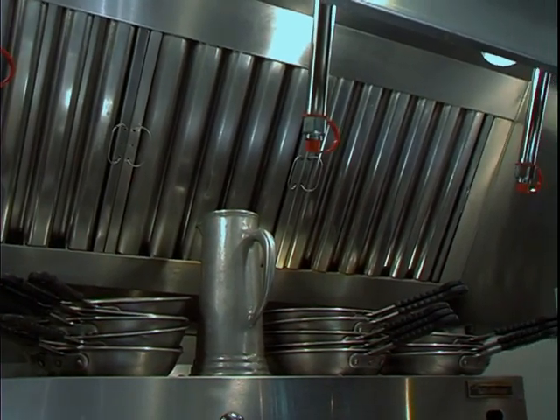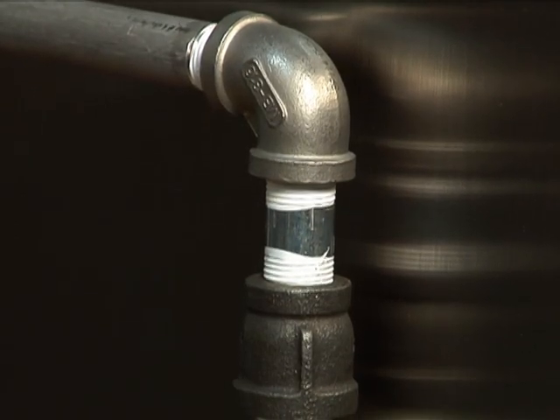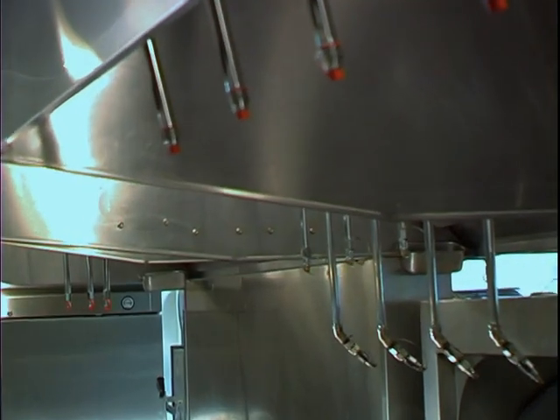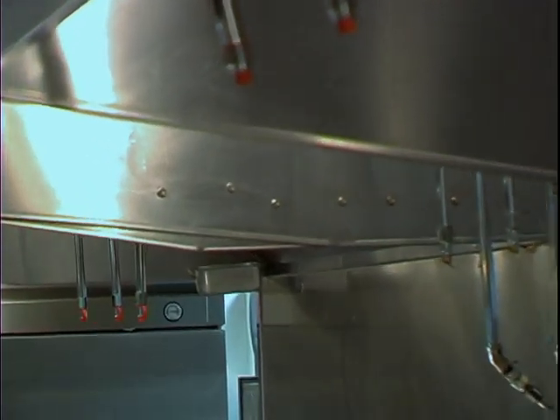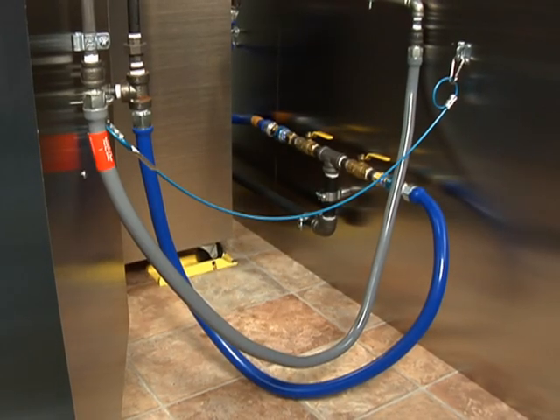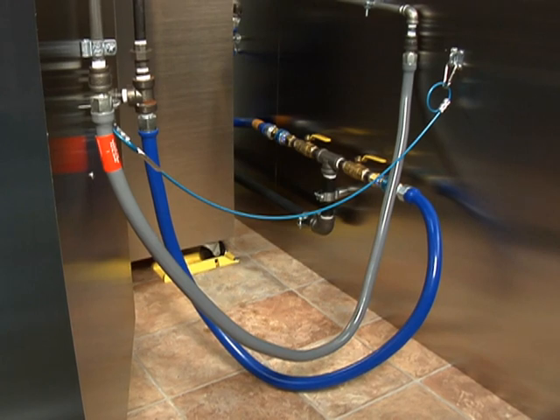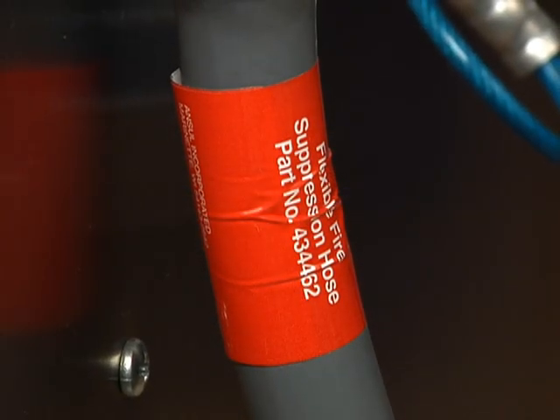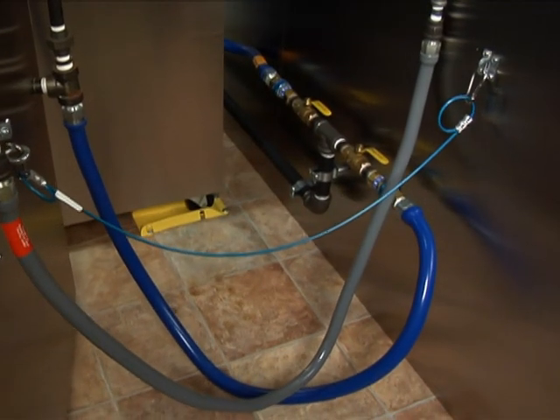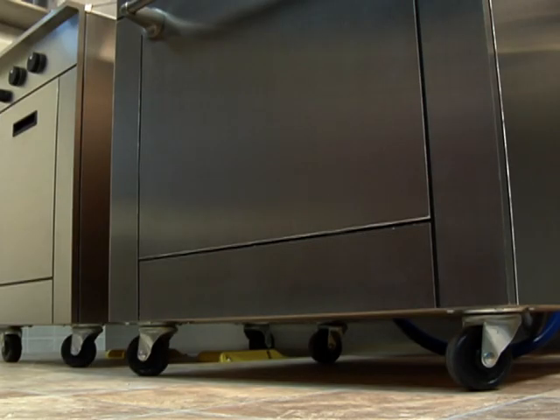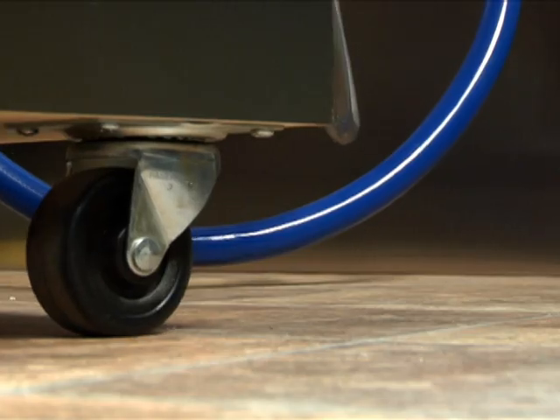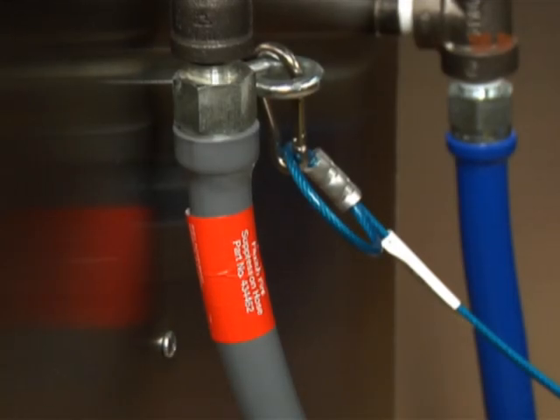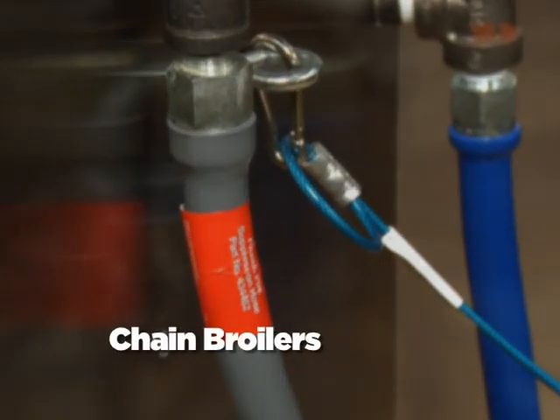Keeping a restaurant's kitchen clean is an ongoing challenge. Often, cooking appliances are hard-piped with the fire suppression system, which does not allow for movement of the cooking appliance during the cleaning process. With the introduction of the flexible agent distribution hose, exclusive to ANSUL restaurant fire suppression systems, it is now easy to clean beneath and behind kitchen appliances. The flexible agent distribution hose conveniently allows castered appliances to be temporarily moved for cleaning. When finished, the appliances are carefully returned to their operating position. The flexible agent distribution hose can be used with any type of castered appliance within the system, including upright broilers, chain broilers, pizza ovens, ranges with back shelves, and salamanders.